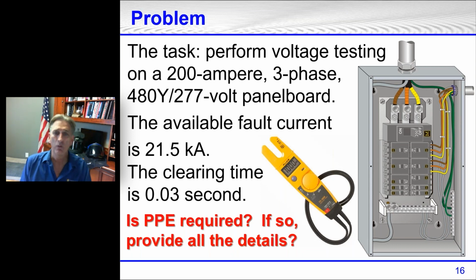Anyway, we've got a 480 volt system. That's what we need to think about and keep in mind. I'm giving you the fault current, I'm giving you the clearing time, or else we're not going to be able to use the tables. Well, okay, so now my question is, is PPE required? Arc flash PPE, is it required? Now we're going to look on the table, we're going to find this, but think about this. If I'm asking you, do you think arc flash or arc rated PPE is going to be required?